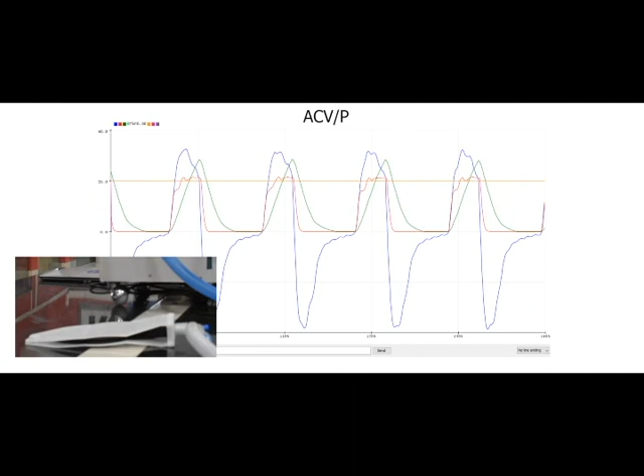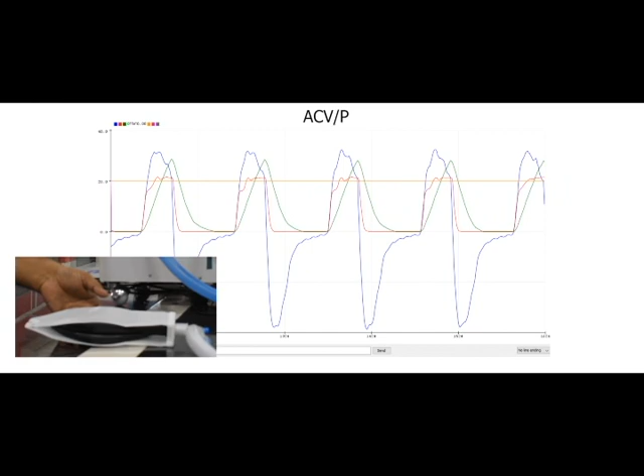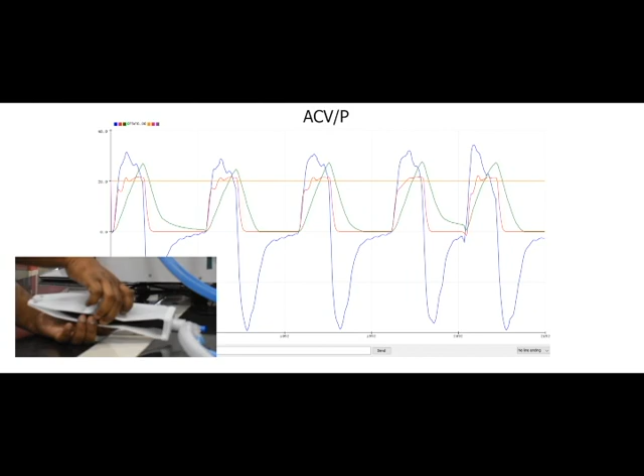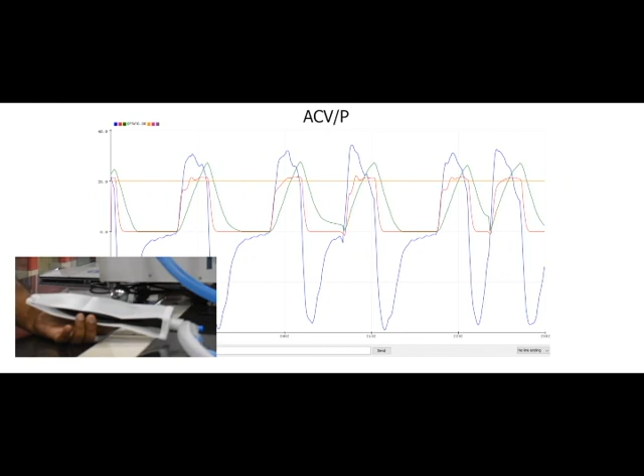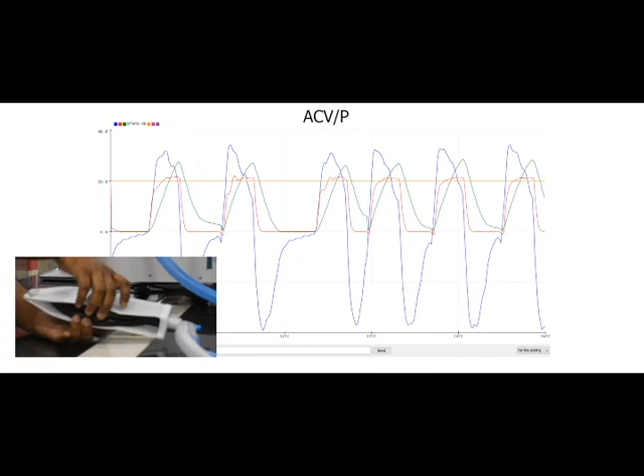Now you can see that the CMV mode is running with pressure control. Whenever I trigger the test lung over here, you can once again find that it is being supported at the constant pressure. Let me show you the same feature. You can see now that the mandatory ventilation is going on to maintain that constant pressure. Whenever the patient triggers his own breath, that will also be supported at the constant pressure, right? Let me show you. So I am giving the triggering, which is set at -2 cm of water column. You can see that the patient is taking the breath and it is being supported in constant pressure mode by the ventilator. Okay, so several times I am doing that to show you the demonstration of the same, right?